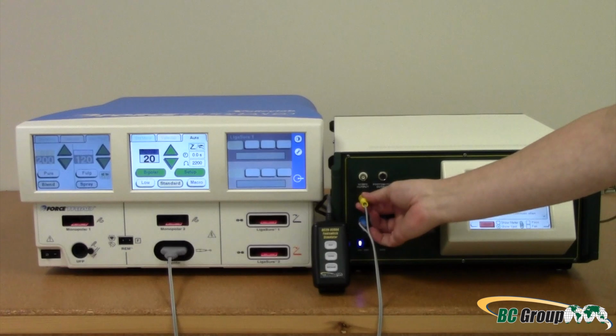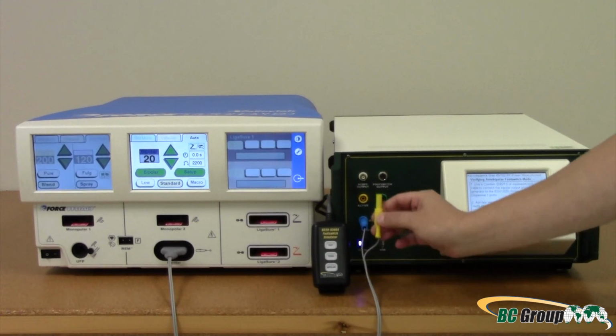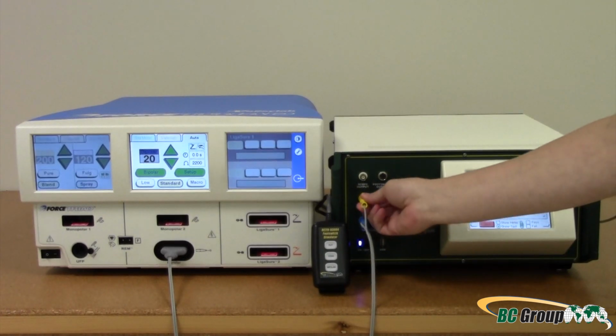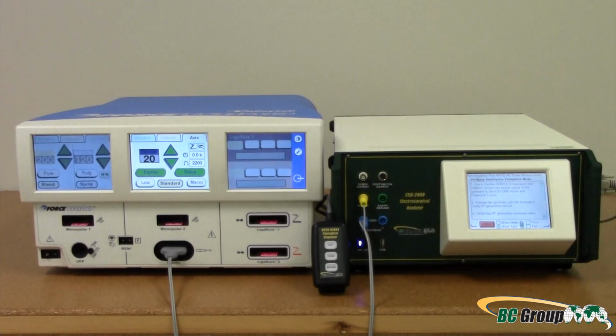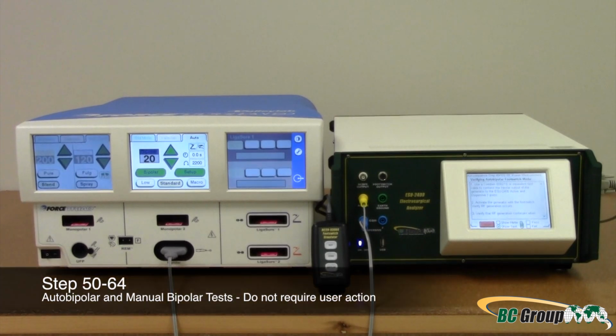Disconnect one of the test leads from the ESU-2400. Verify that RF generation stops. If RF generation stops, reconnect the test lead to the ESU-2400 and then press the Pass checkbox. Steps 50 through 64 do not require user action.